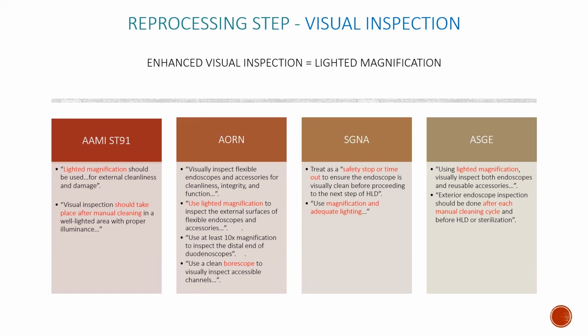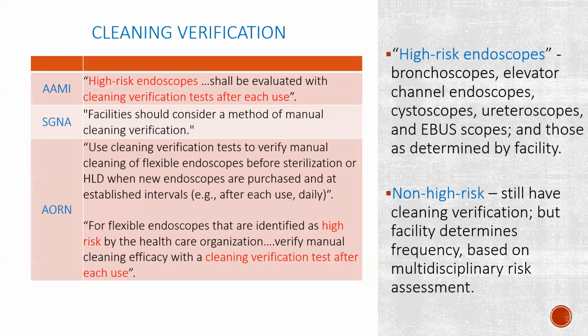All organizations promote the use of light and magnification as part of focused inspection following manual cleaning. Lighted magnification is what we mean when we call out the need for enhanced visual inspection. We're purposely enhancing what we can see with the naked eye. SGNA highlights inspection as a unique step that serves as a safety stop or a timeout. And they note that it's the minimum standard for cleaning assessment. AORN directly promotes the use of borescopes for accessible channels. Any soil and or biofilm that remains after cleaning can interfere with the disinfection or sterilization process. So cleaning verification is part of focused inspection. It is AAMI, AORN, and SGNA that speak to the need for cleaning verification testing as part of inspection after manual cleaning.